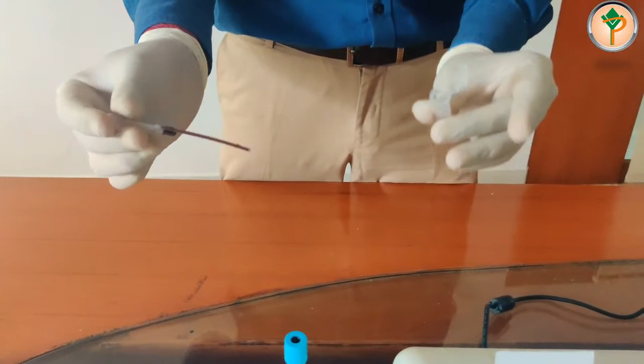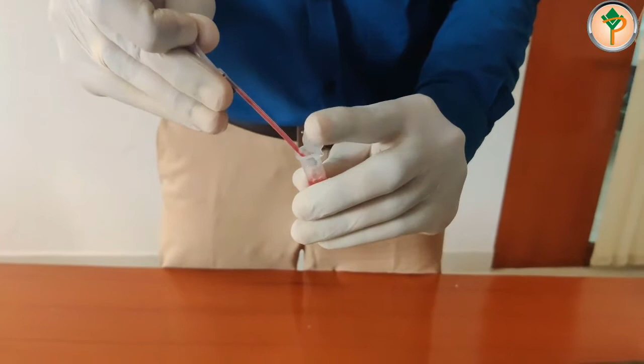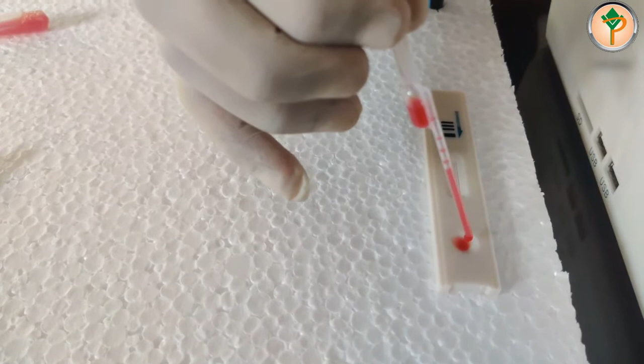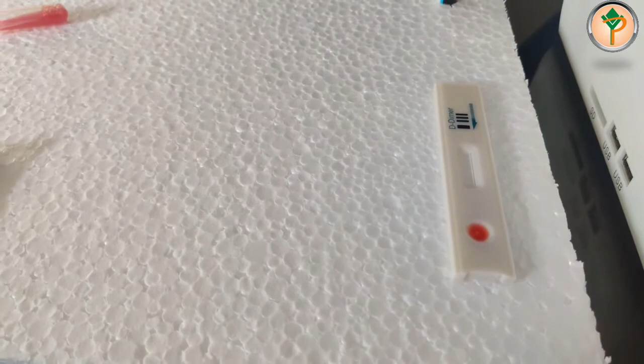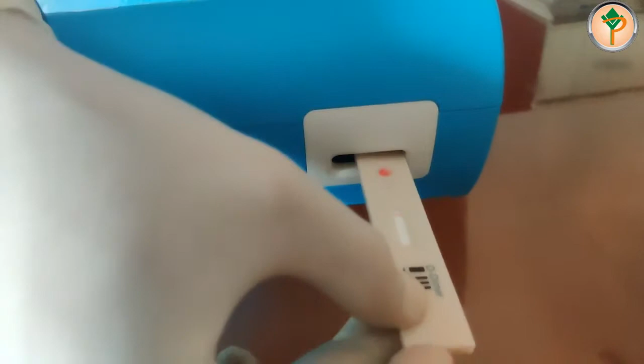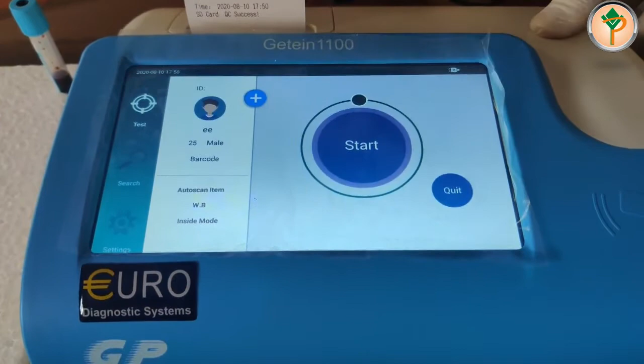Now I am mixing the sample with diluent. You have to mix it 10 times. So after mixing, from the diluent, I will take 100 microliter. You have to add the sample to the test card. Take the test card, immediately insert it in the slot. Then press the start button.